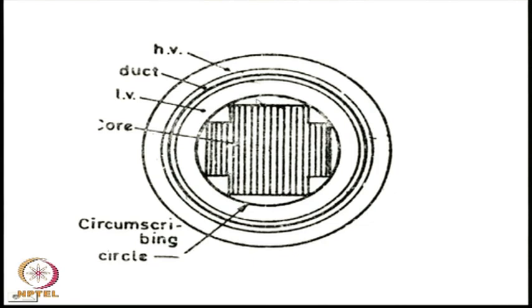Now, ideally the core cross section should have been a circle, but cores also need to be laminated. If a very good approximation to this circle is made, then laminations of continuously varying width will be necessary, which is problematic from the point of view of production. Therefore, a compromise is arrived at. Generally the cores are made in step form. This is called a cruciform core with only 2 steps. For larger transformers, an even larger number of steps, 5, 6, up to 6, is used, so that the circular space is more maximally utilized.